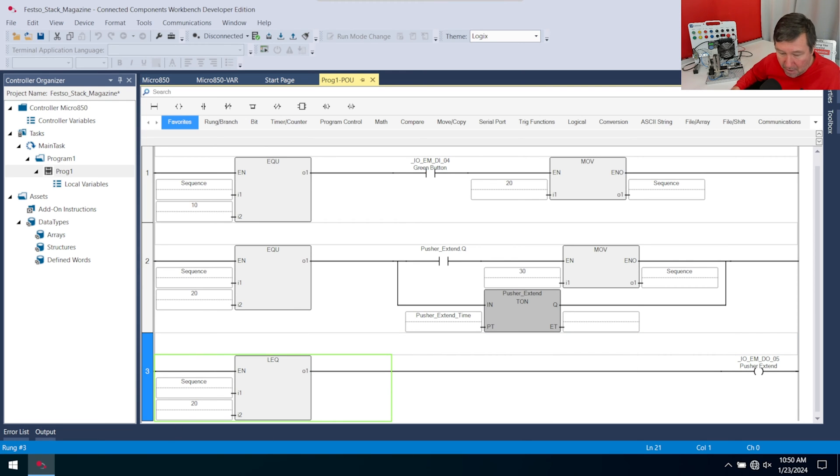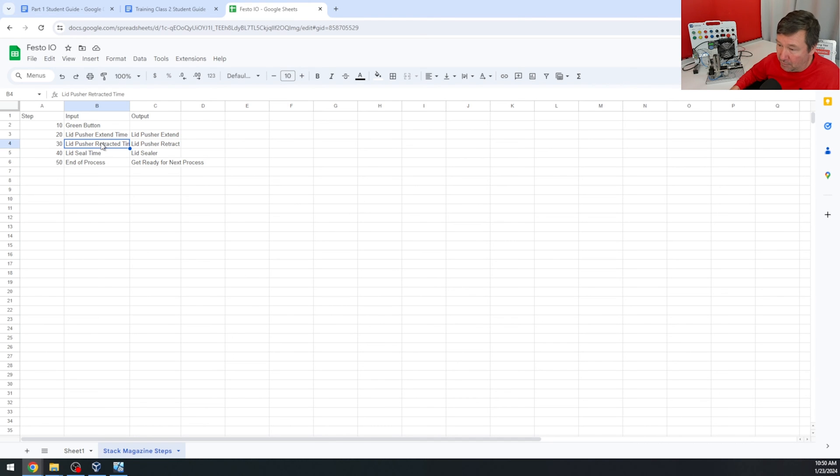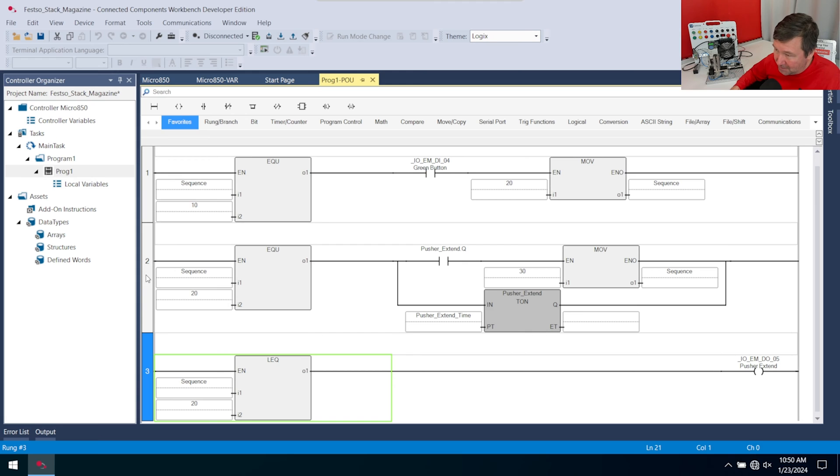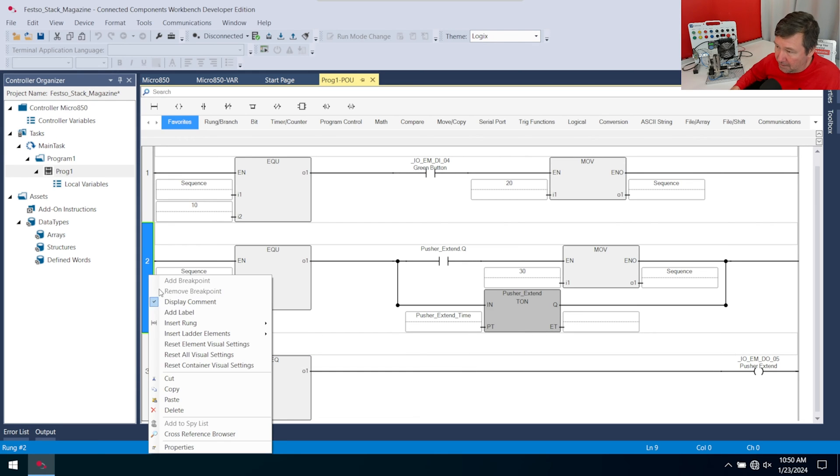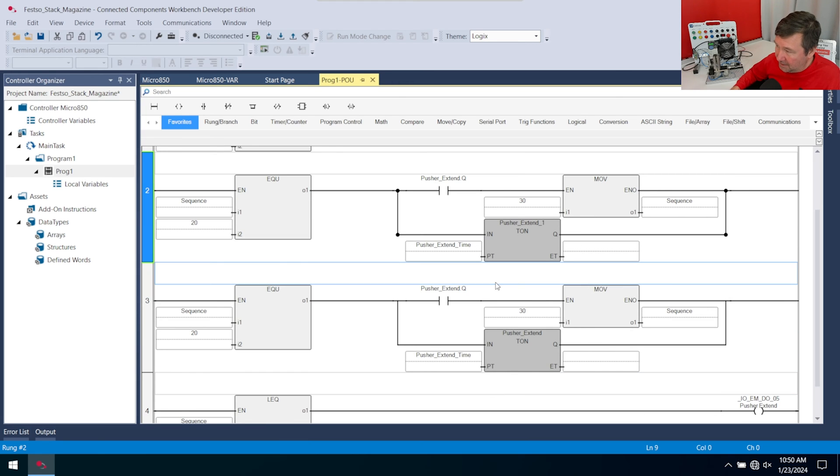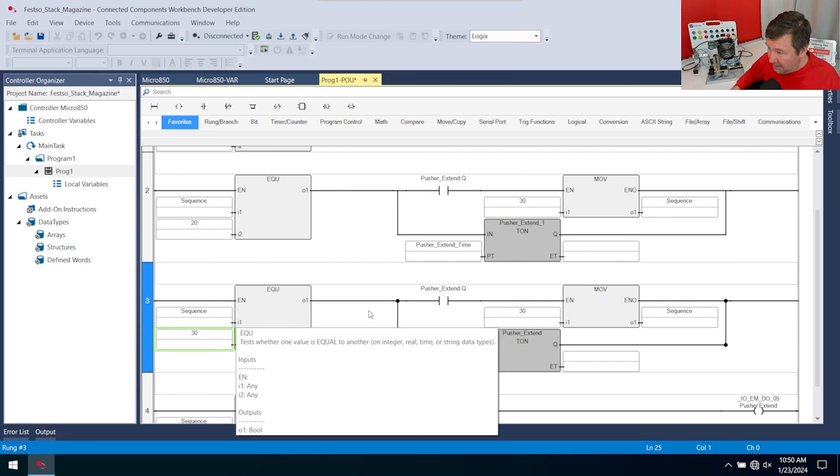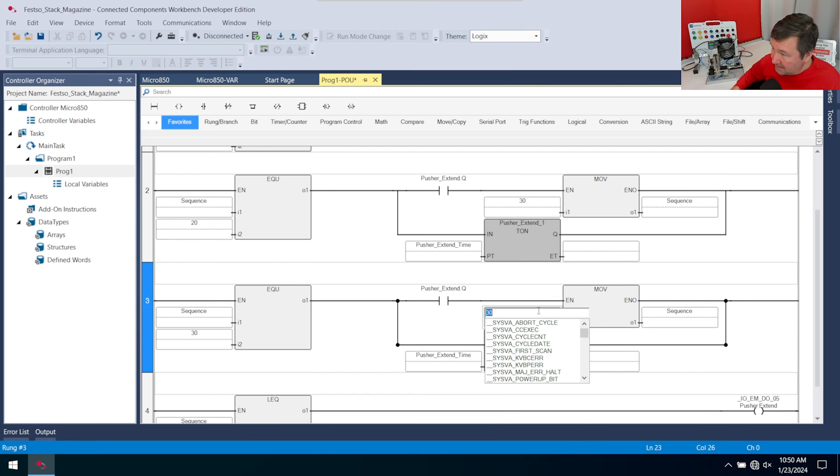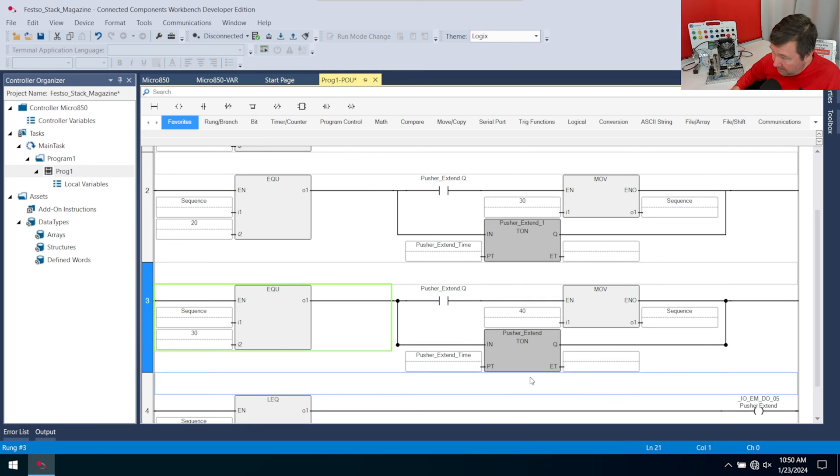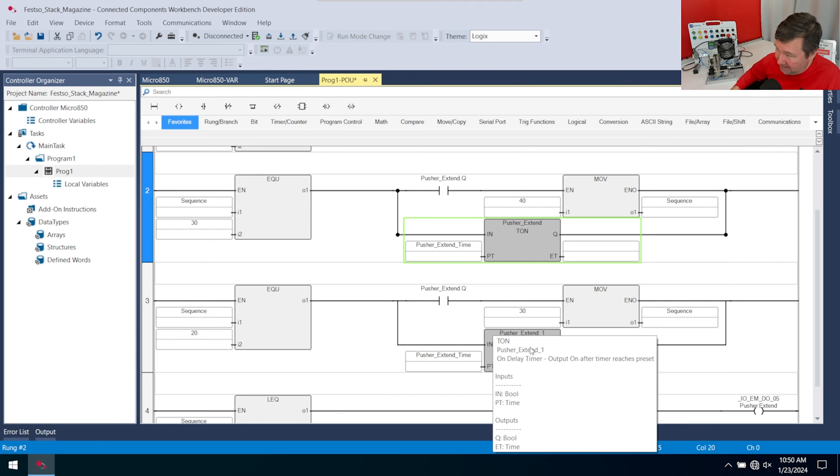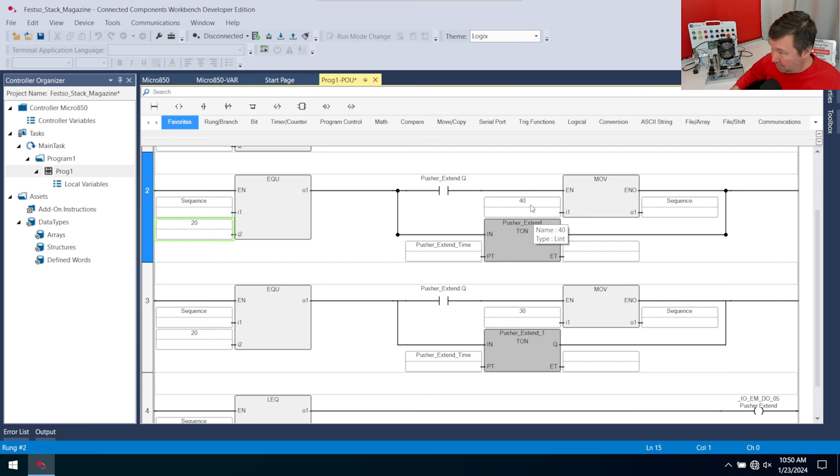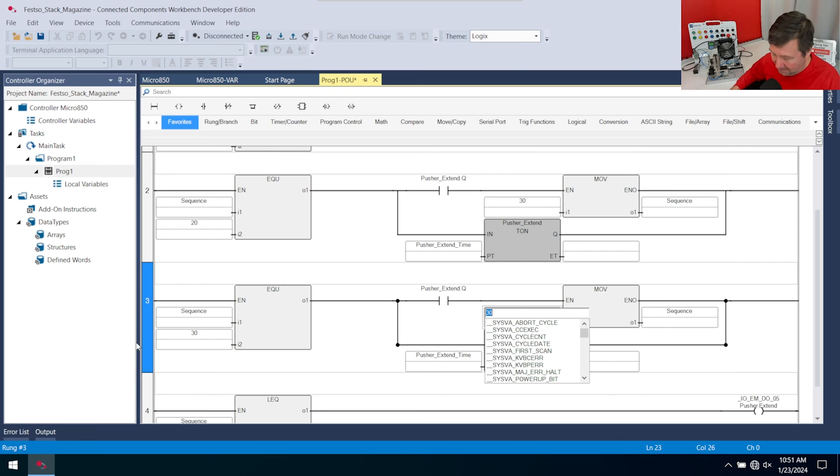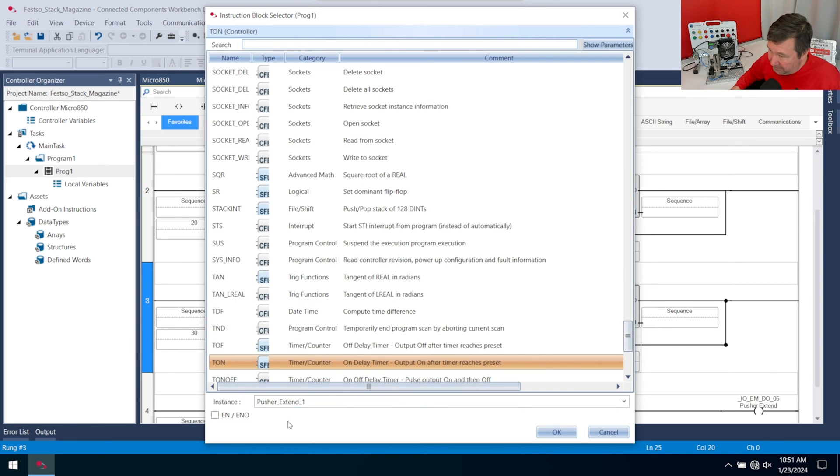That gets us to step number 30 in our process, and step number 30 is pusher retract. We're going to have a pusher retract time. That is really close to what we have in rung two, so we're going to copy and paste. Copy rung two, paste it right back. We want to be really careful not to get our numbers confused because now we want it when this is equal to 30, and we're going to want to move 40 when we're done. I just noticed I made a big mistake because this one needed to be up here because this was our pusher extend. This one should have been 20 and 30, and this one should have been 30 and 40.